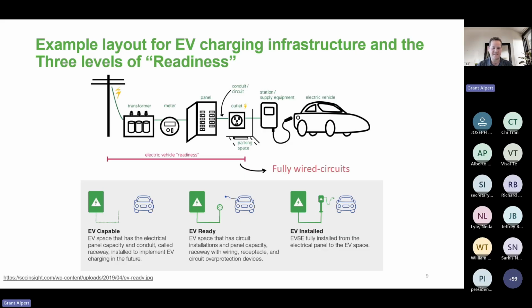Speaking of EV charging, EV ready, EV capable, here's the whole diagram. It goes from the transformer to the meter to the panel to the circuit, the outlet, and then the supply equipment, the EVSE, EV supply equipment, or EV charging station. There are three levels of readiness defined in the code. The first is EV capable, which is what I mentioned earlier regarding non-residential buildings having to use previously installed EV capable spaces before installing new infrastructure. If there's electrical panel capacity and conduit already installed, that's an EV capable space, but there's nothing above ground indicating that an EV can be charged there.